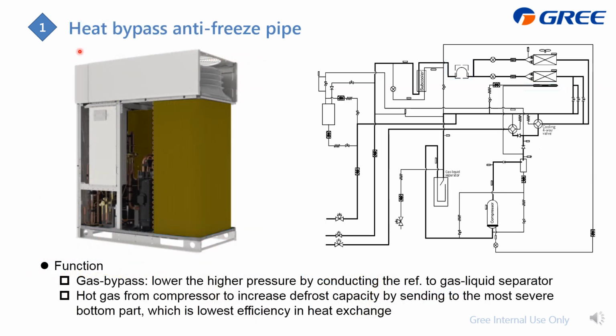The heat bypass anti-freeze pipe is located at the bottom side of the outdoor heat exchanger, which means at the bottom side, this part is not the same as the upper side. You can find that for the ventilation system, if it is far away from the upper fan motor, the air volume will also be poor, which also indicates the heat transfer amount at this part is very poor.